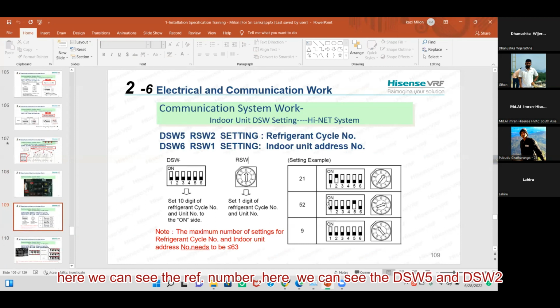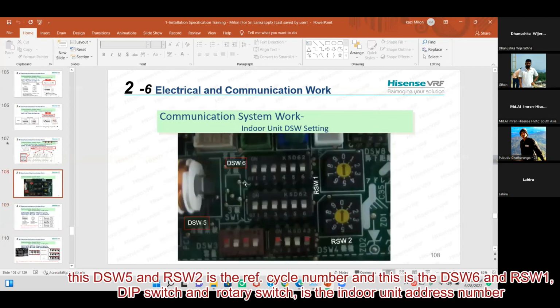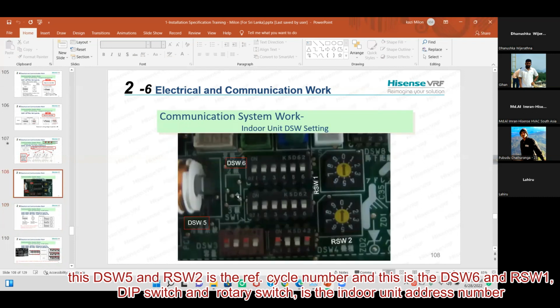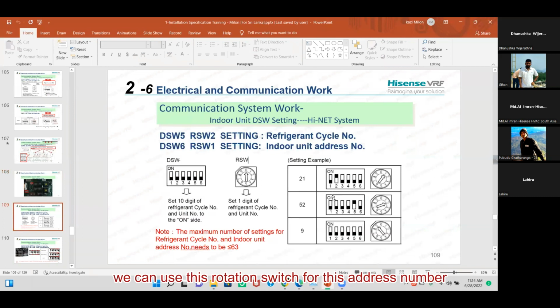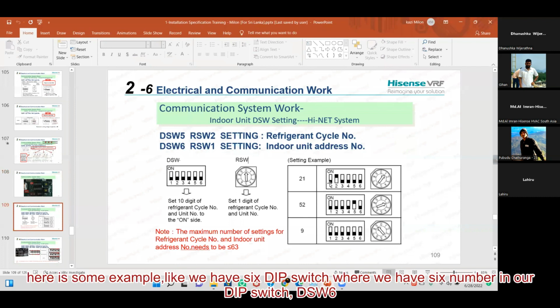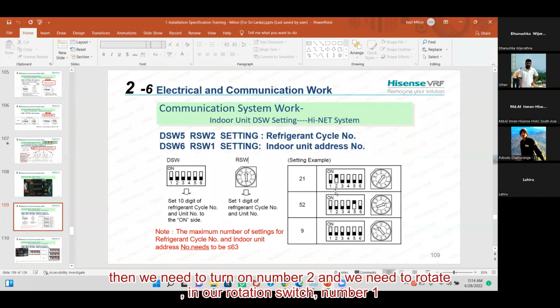Here we can see the refrigerant cycle number. Here DSW5 and RSW2 is the refrigerant cycle number. And DSW6 and RSW1, that means DIP switch 6 and rotary switch 1, is the indoor unit address number. We can use this rotary switch and this address number. Here is an example: we have a 6-digit DIP switch, DSW6. Then we need to turn on number 2, and we need to rotate our rotary switch to number 1.